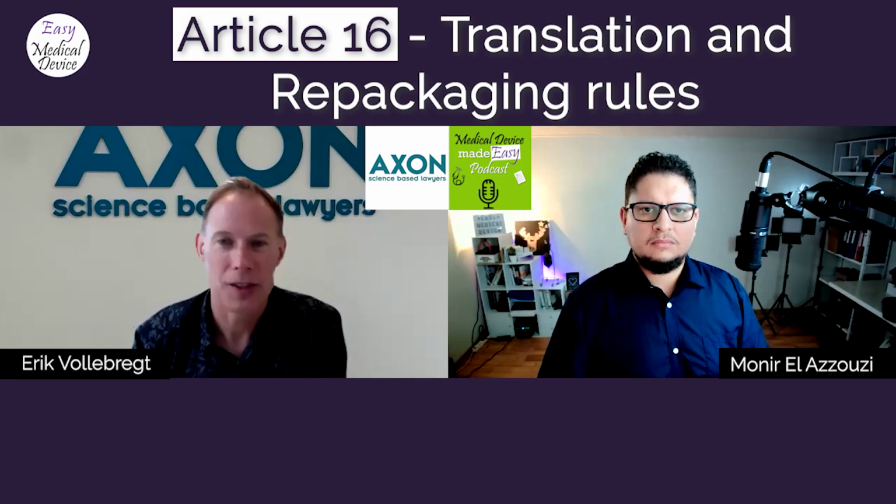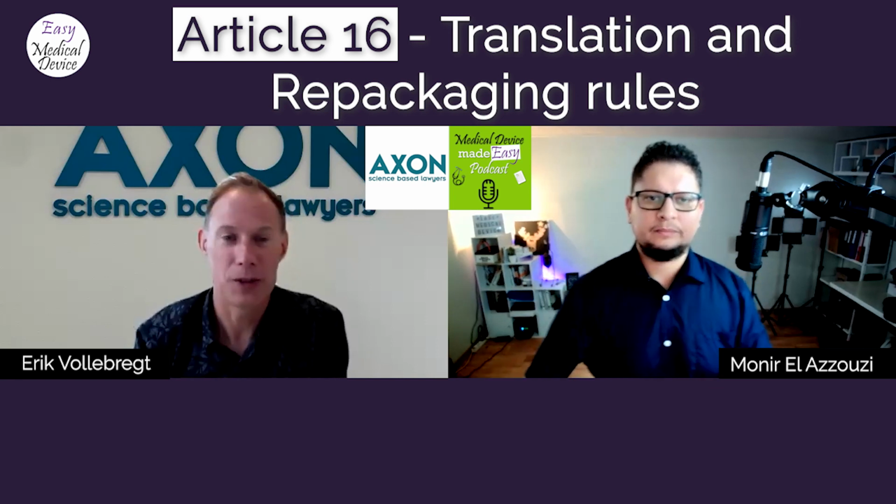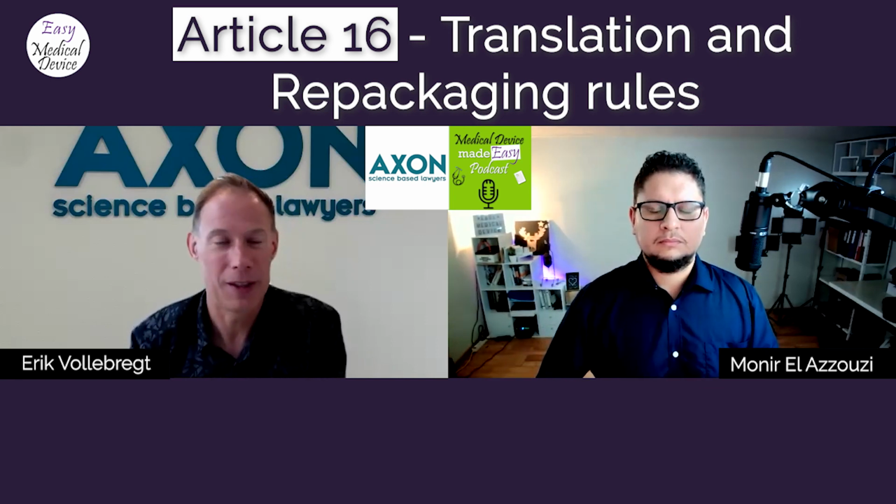The point is basically that the MDR and the IVDR view the activity in Article 16.2, so translation and repacking, contrary to the case law of the European Court of Justice that we had before the date of application of the MDR, as a quality system controlled activity, subject to notified body surveillance. That's how the MDR sees it. And that means that you need a notified body.